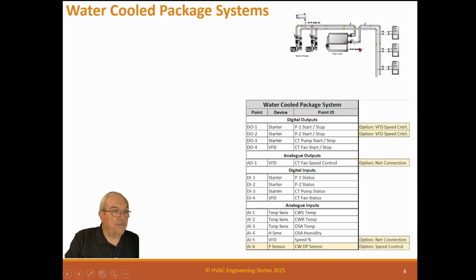Now, the reason I put VFDs on these, you could put just a starter on them. But over the years, I've discovered that every cooling tower fan, fluid cooler fan, or refrigerated fan needs to be on a VFD. It just works out that the condensing temperature is always fluctuating, so the fan is always going to be modulating, not at full speed. And it will save you energy. It pays back in less than 18 months, every one I've ever calculated. I got to where I just gave up calculating because it's just a good deal.